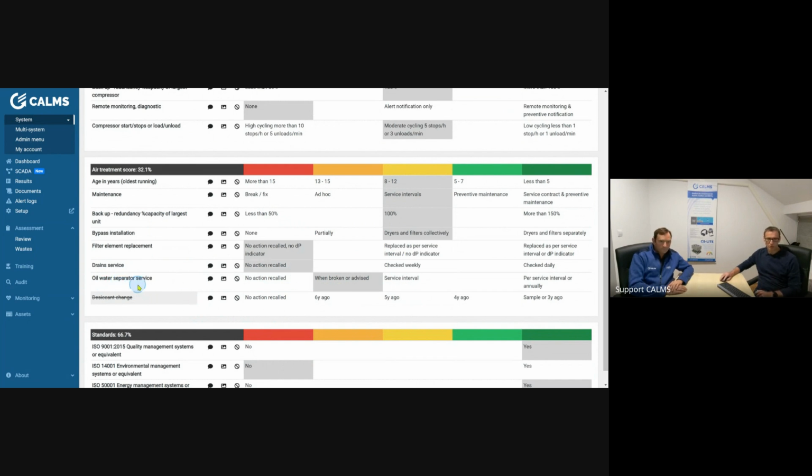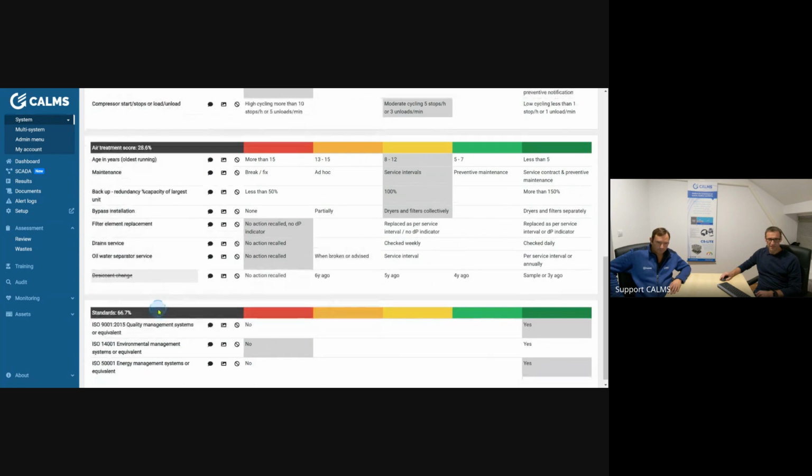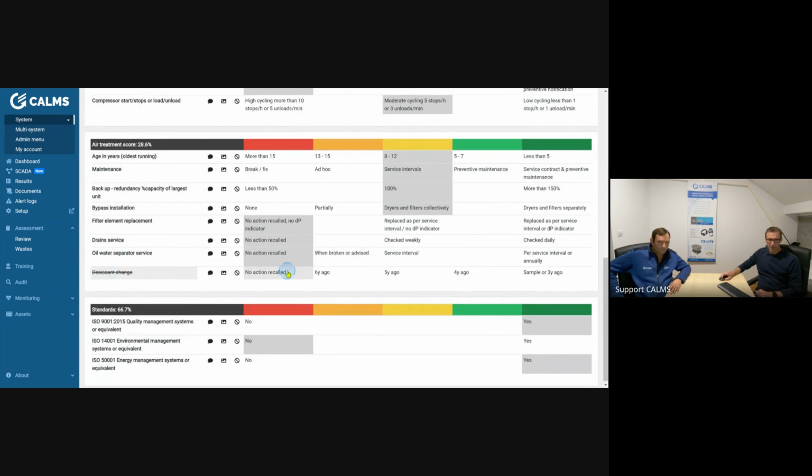And then we have also the water separator. Do you have one? We noticed it's a lot of oil around the water separator. I'm not worried about that oil. There's a lot of oil on the floor. Yeah, on the very floor. Slippery. Exactly. Yeah, very slippery. So maybe yes, maybe we would need to take care also about this, because it could be an environmental issue. This is very important these days. Yeah. Exactly. So the second dryer, you don't have it.